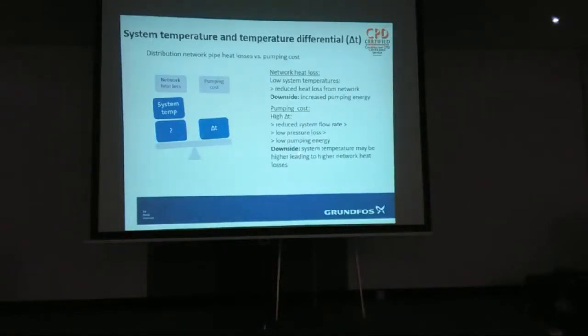On this one here, you might end up having a higher flow temperature with a wider delta T, like 80-40 or 80-60, something like that. So if your system's not well insulated, you could lose a higher proportion of your temperature. So it's a bit of a balance. That's on the design and installation side. These are things that we picked up on over the years.